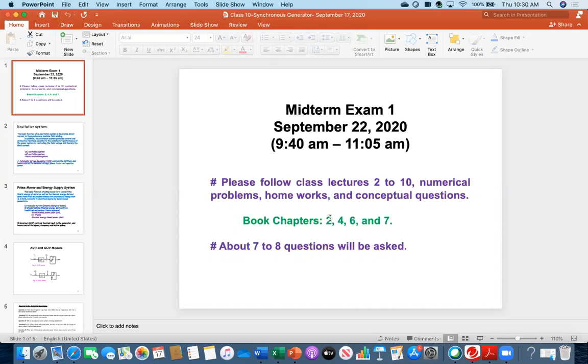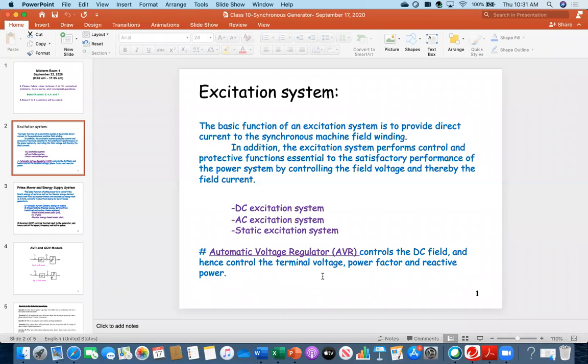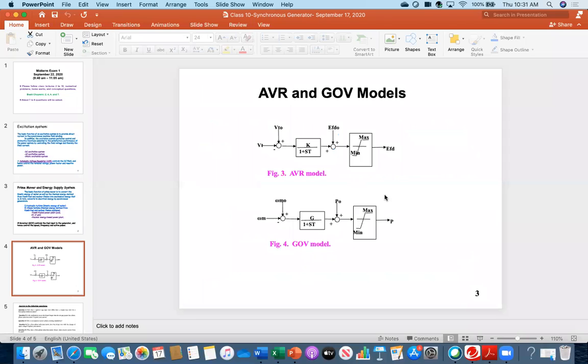Moving to today's lecture — last time we were discussing the excitation system. There are three types: DC excitation, AC excitation, and static excitation. For the excitation system there is a controller called the Automatic Voltage Regulator, or AVR. The AVR controls the DC field current, and hence controls the terminal voltage, power factor, and reactive power.